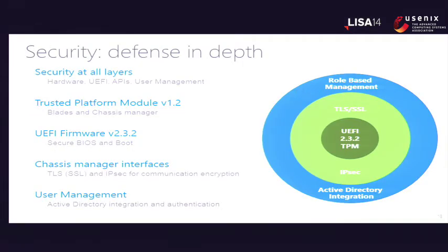Security, so systems management. Imagine if somebody gets access to this management network, they can turn the whole data center off, which is scary. So you want to make sure that there is an adequate amount of security built in. What we have done here is just typical security policies, defense in depth. First, the chassis manager card, which is used for out-of-band access, has a TPM on it, so you can do your secure boot. After you boot it up, the command interface is through SSL, so your commands are encrypted, and the certificates are set up before that, of course.